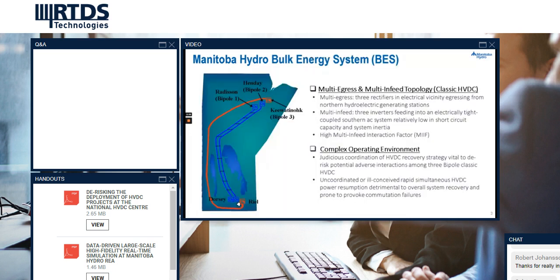Manitoba Hydro's transmission facility has been developed and operated as an integrated system, with the bulk energy system being the three LCC HVDC transmission lines, namely Bipole 1, Bipole 2, and Bipole 3, commonly known as the Nelson River HVDC system. Vintage Bipole 1 and 2 originate in the north from the Radisson and Henday rectifier stations respectively, share the same interlake corridor, and terminate about 900 kilometers away at the Dorsey inverter station in the south.